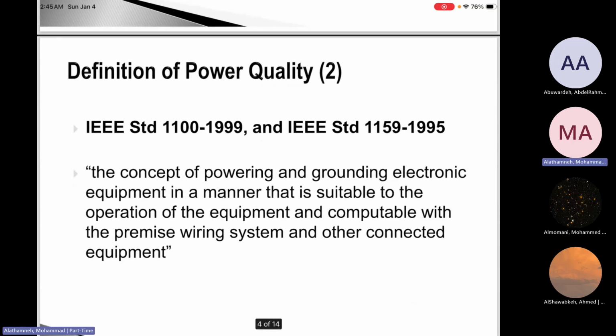So, definitions of power quality standards in IEEE framing. We can connect IEEE standards to power quality, to maintain that the system is working well regarding power quality problems. Here we can see the references IEEE 1100, the Emerald Book, and IEEE 1159. IEEE 1100 focuses on powering and grounding sensitive electronic equipment, and IEEE describes it as a collection of consensus best practice to enhance equipment performance while maintaining safety.